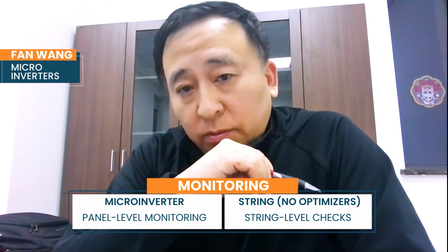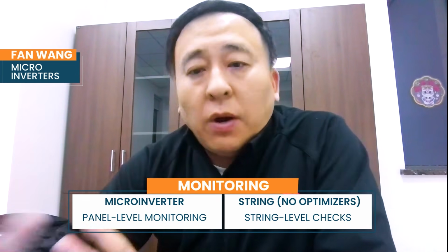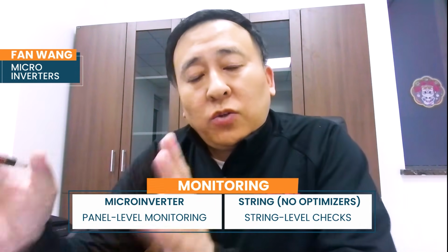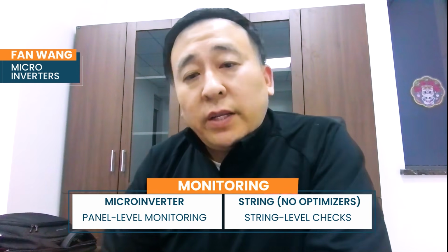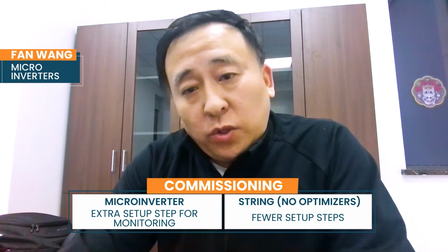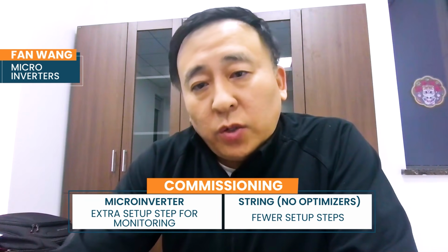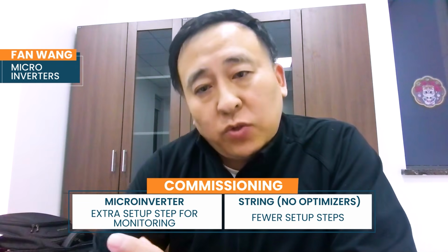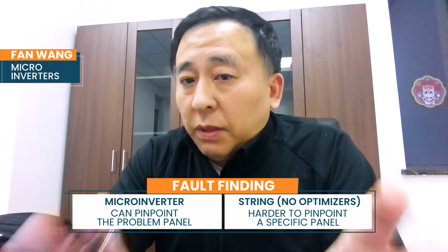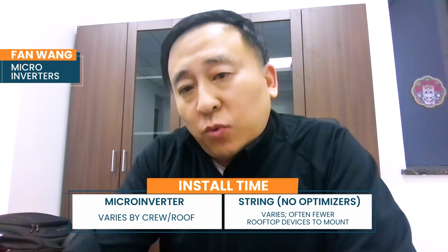Given the extra work in commissioning, Fan, do microinverters have more chances of errors during installation than string inverters? I'd say it this way: most microinverters have panel-level monitoring, which is a bit different compared to the traditional string inverter without an optimizer. If you talk about a string inverter with an optimizer, it's virtually the same as a microinverter for installation and commissioning. But for the traditional string inverter without optimization, you don't have panel-level monitoring—you just measure the string voltage and connect things together. For microinverters, that's one additional step. We've developed several tools, from apps to hardware, to try to simplify this step, but it is an additional step compared to the string inverter. Even so, if something's wrong with a panel, you know exactly which panel has the problem. People are willing to pay a little extra in labor for this, but compared to the long-term benefit, I think it's worth it.